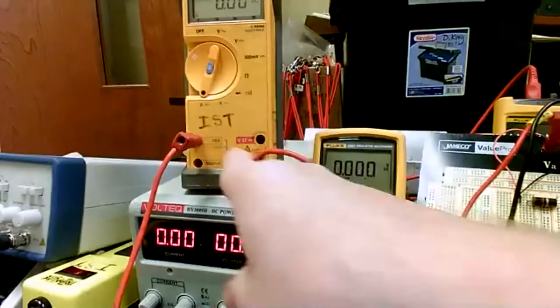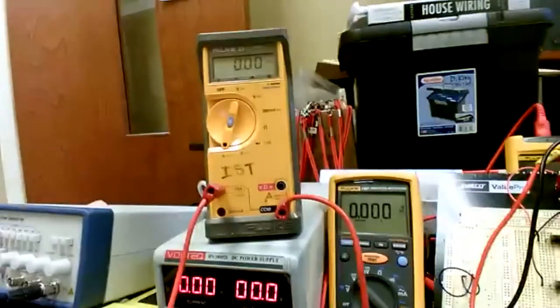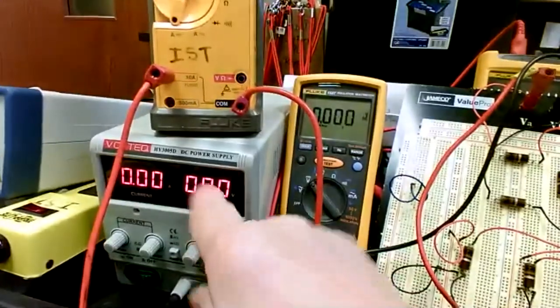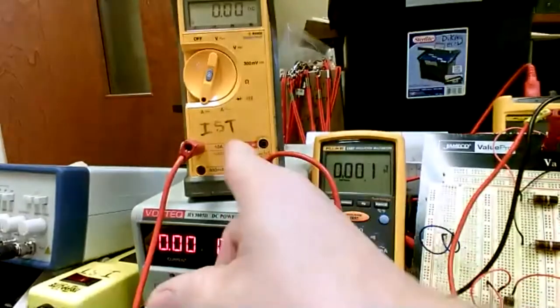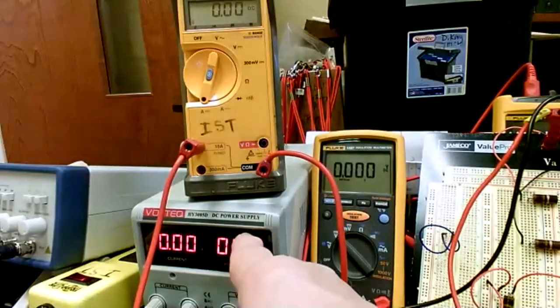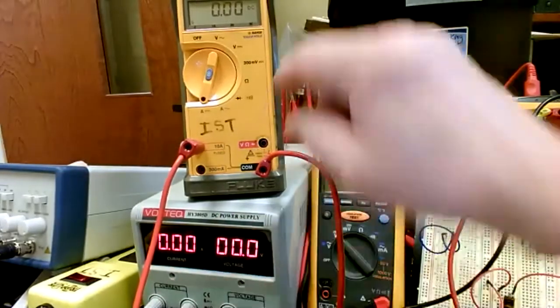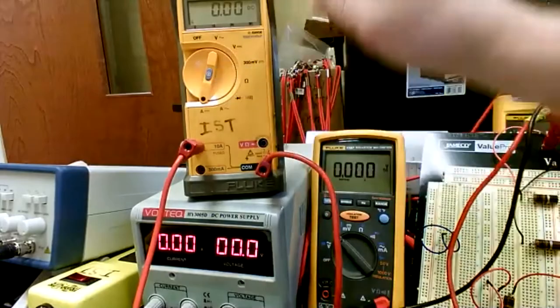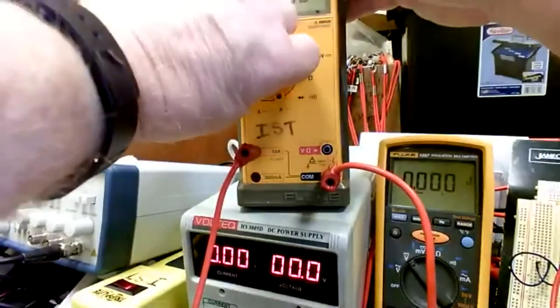I'm going to do that, but before, anytime you're using an inline ammeter like that, you actually want to power down the circuit that's feeding through the ammeter.